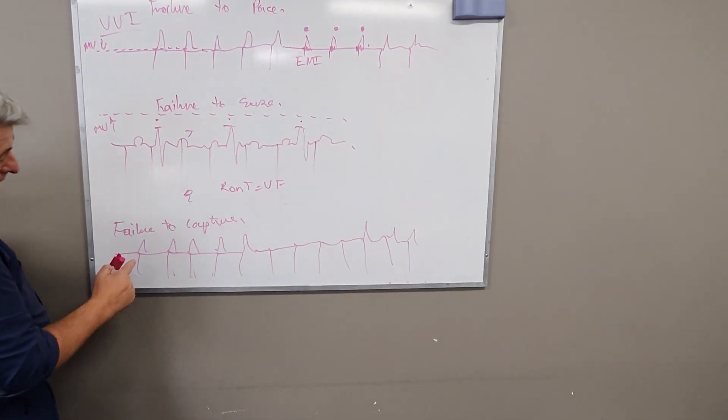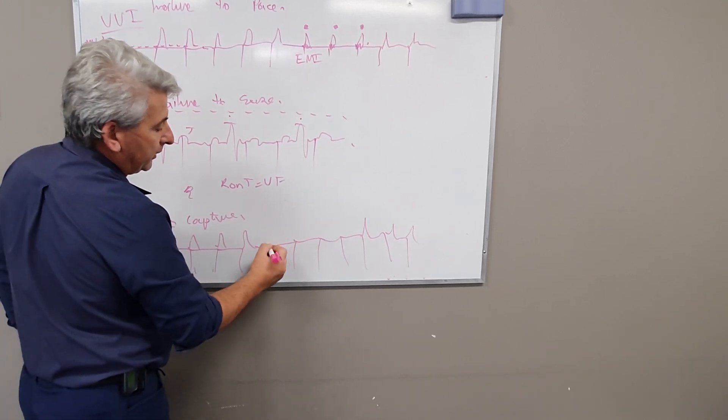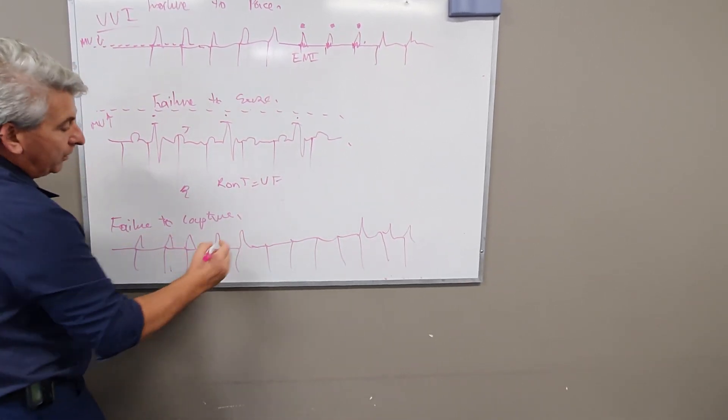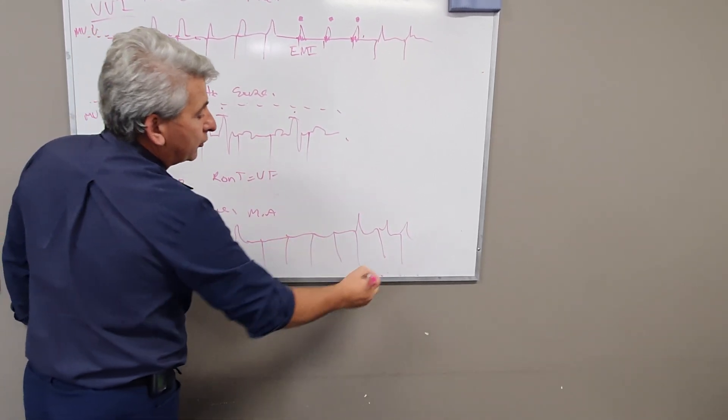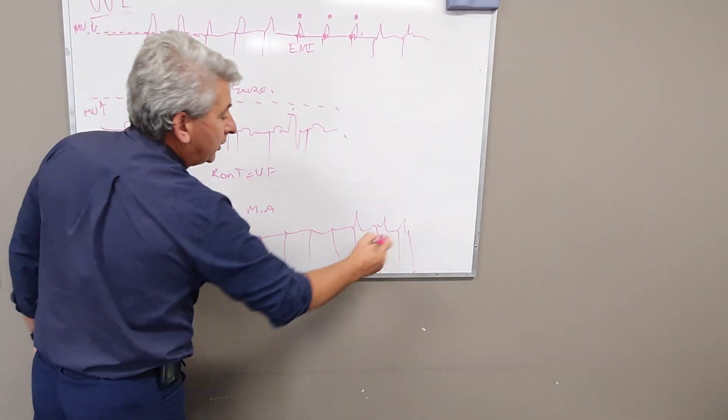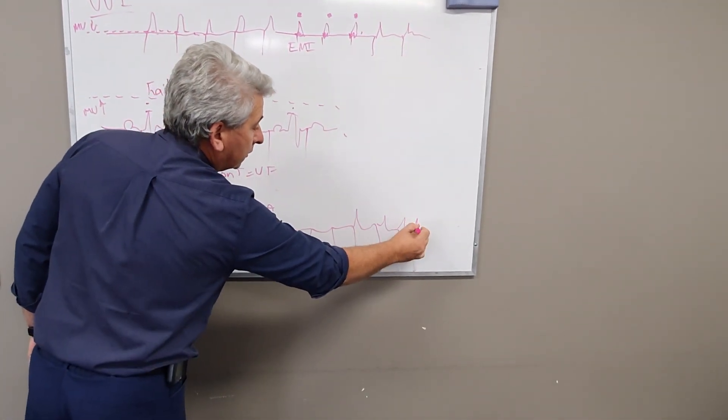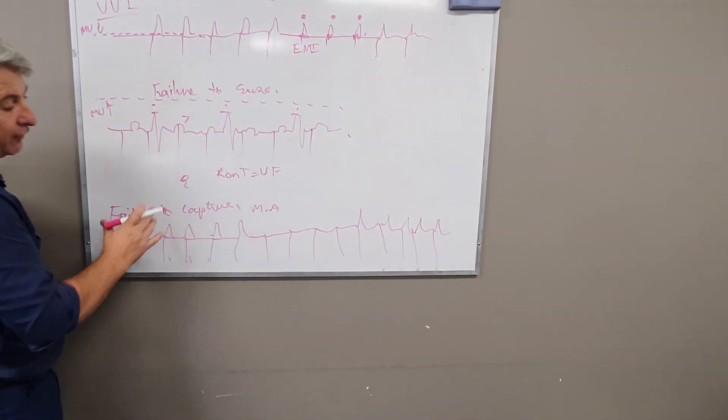So what's happened here is pace, capture, pace, capture, pace, capture. Here I pace, pace, pace, but not followed by any capture. All it means is your milliamps are too low. Increase the output, or the milliamps, so theoretically making the pacing spike longer, and that will always then result in a rectification of the failure to capture.